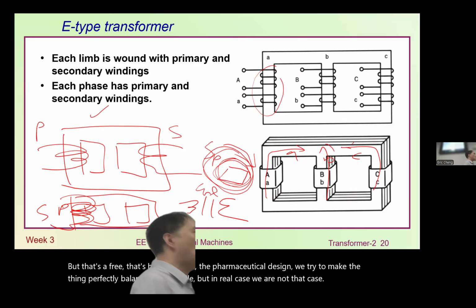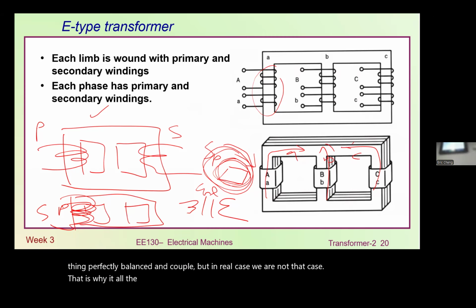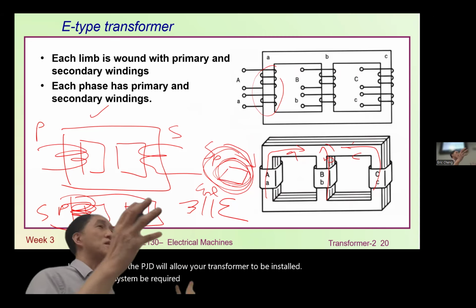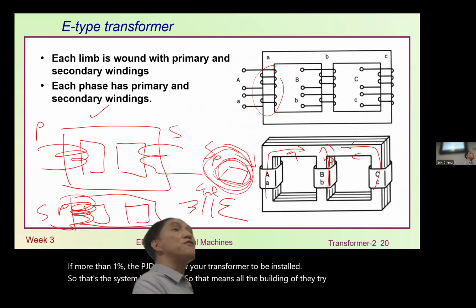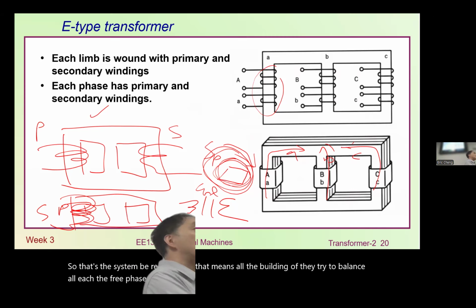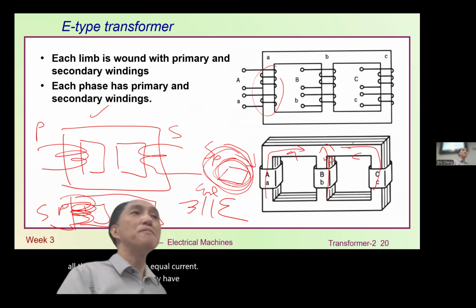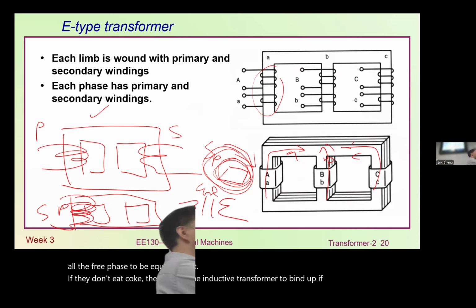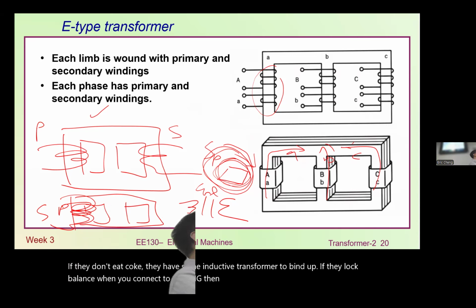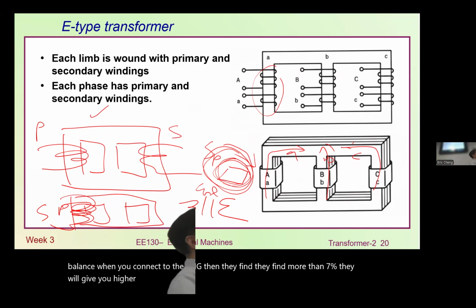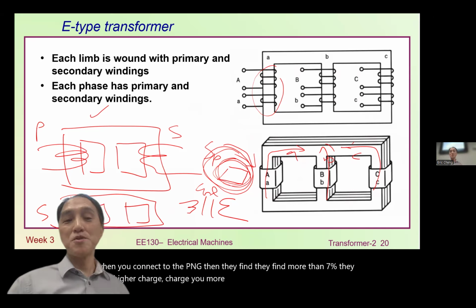That is why in all transmission systems, they require the system to be perfectly balanced, with imbalance allowed down to only 1%. If more than 1%, PG&E will not allow the transformer to be installed. So that's the system requirement. That means in every building, they try to balance each of the 3 phases to equal current. If they don't, they use inductors or transformers to balance it out. If it's not balanced, when you connect to PG&E and they find the imbalance is more than the allowed amount, they will charge you more on your electricity bill. That's how the system works.